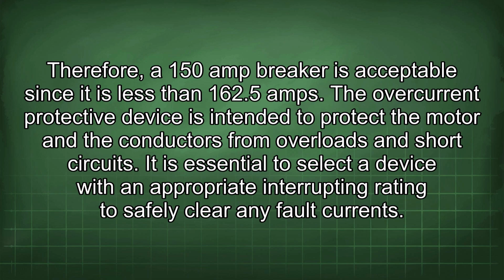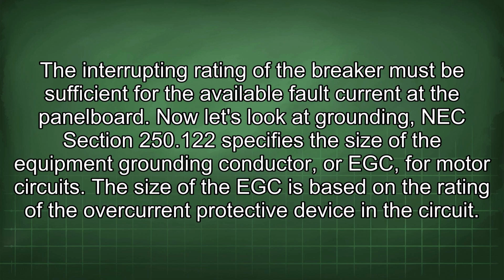The overcurrent protective device is intended to protect the motor and the conductors from overloads and short circuits. It is essential to select a device with an appropriate interrupting rating to safely clear any fault currents. The interrupting rating of the breaker must be sufficient for the available fault current at the panel board.